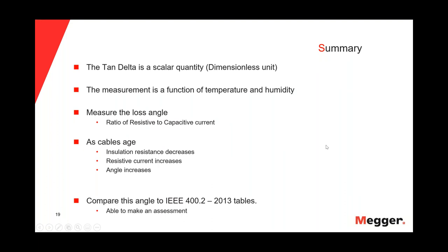The Tan Delta is a scalar quantity and dimensionless unit. The measurement is a function of temperature and humidity. It is the measure of the loss angle — the ratio of resistive and capacitive current. As cables age, the insulation resistance decreases, the resistive current increases, and the angle increases. Compare this angle to the IEEE 400.2 2013 tables and you are able to make the proper assessment.